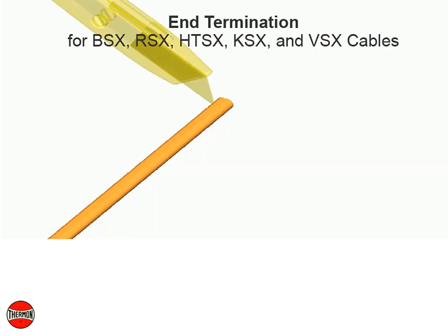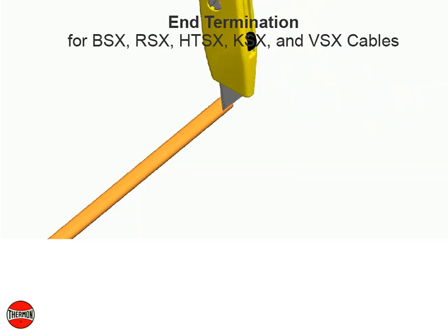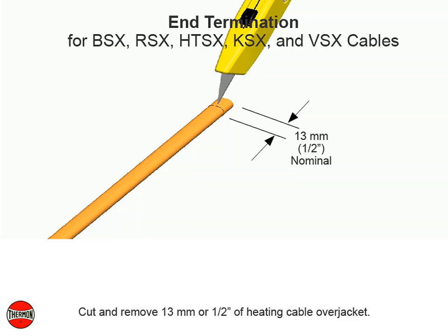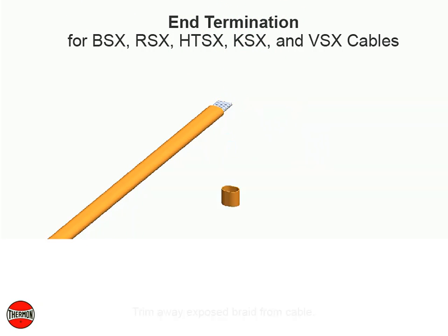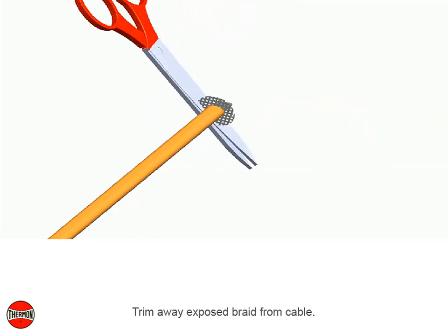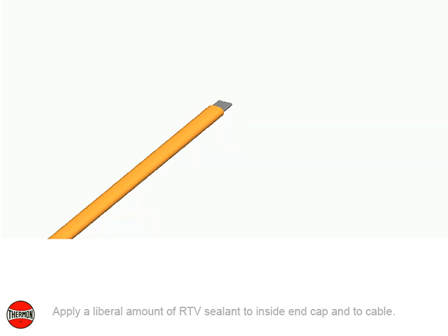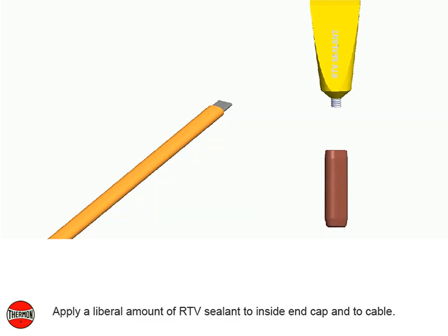End termination for BSX, RSX, HTSX, KSX, and VSX cables. Cut and remove 13 millimeters or 1/2 inch of heating cable over jacket. Trim away exposed braid from cable. Apply a liberal amount of RTV sealant to inside of end cap and to cable.